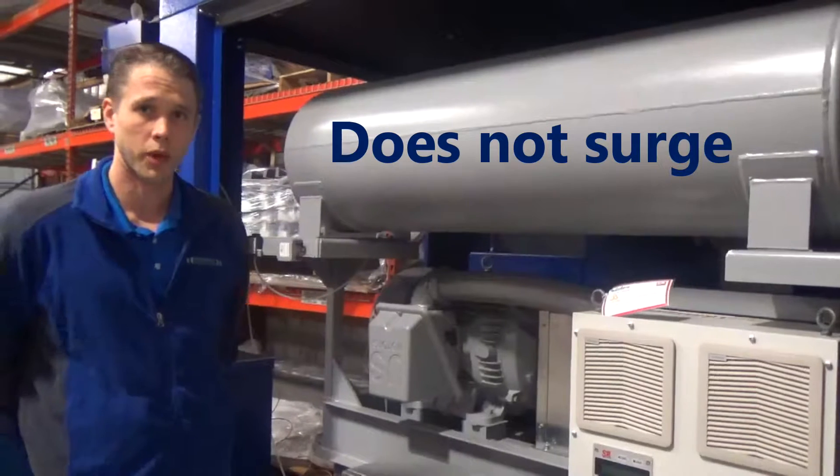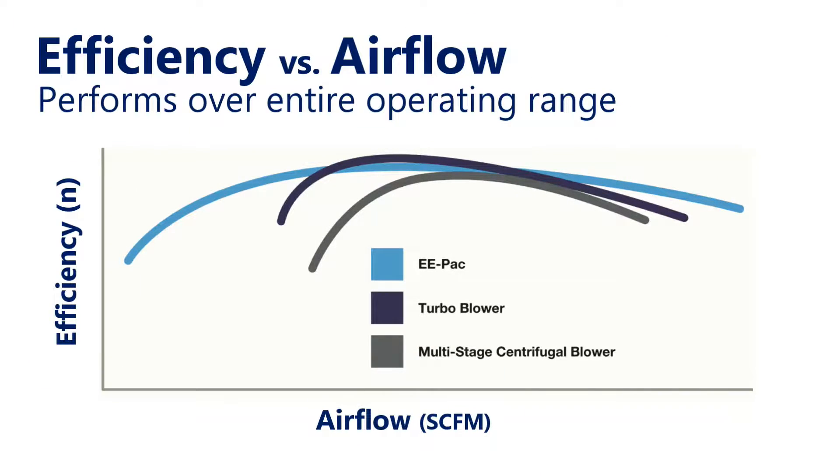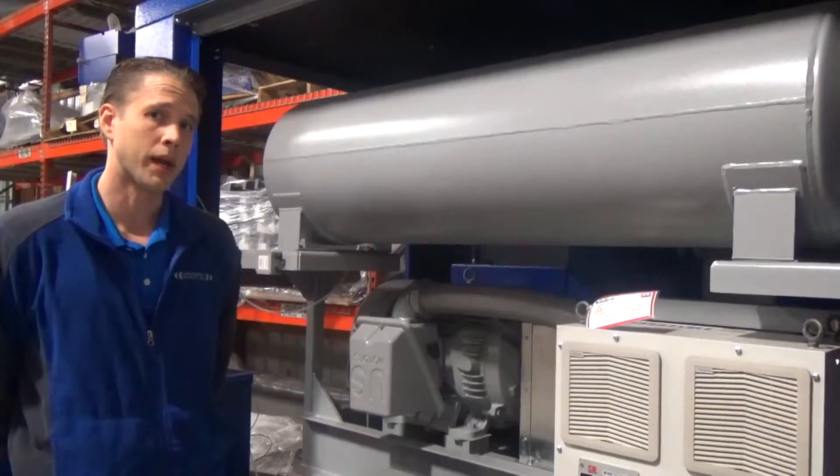The EE-Pac does not experience surge — it's a positive displacement compressor. This differs from turbo blowers, which are dynamic compressors and do experience surge conditions. This means the EE-Pac can be applied in instances where you have a variable line pressure, processes such as an SBR, or even pneumatic conveying.